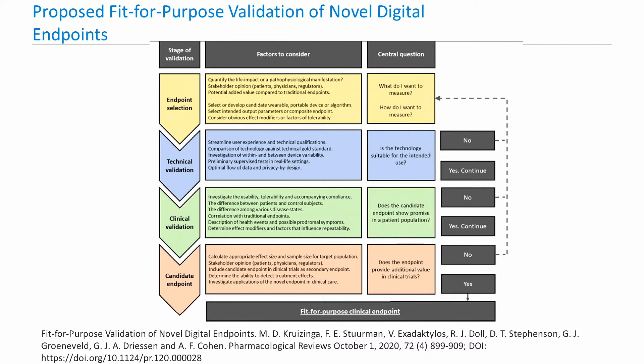The reliability and consistency of the device should be assessed in the form of inter-device and intra-device variability. The lack of these features can introduce issues with interpretation of results. The flow of data should be as automated as possible and should have proper security and privacy provisions. Authors also recommend compliance with necessary regulations regarding audit trails, storage and processing of data. Some analysis should also be conducted with non-patient test subjects to ensure that the novel endpoint measurement actually measures the process you want to qualify in real life. An important consideration is to discriminate activities that might have similar response by the technology.